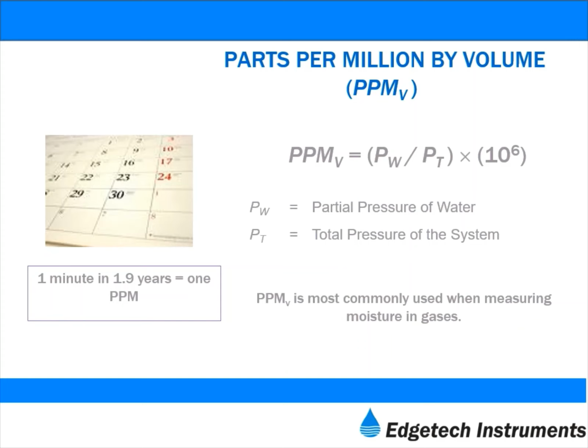So, per the ideal gas law, the simpler way of calculating parts per million would be to measure the water vapor pressure, which is the pressure the water molecules exert, and divide it by the total pressure, which is the pressure all the molecules exert, multiply it by a million, and that will give you parts per million. So there's many hygrometers out there that if they're reading a vapor pressure or a dew point measurement, and a customer or the user is looking for a ppm value, then some math has to be done.